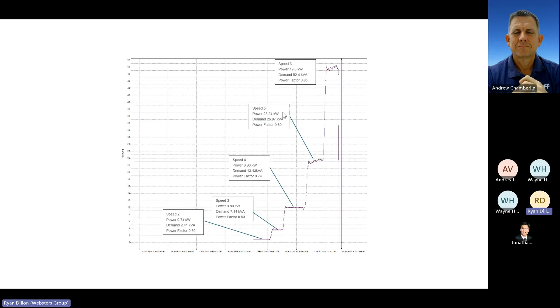And as you reduce the speed, the power factor dropped, which means proportional to the kilowatt demand, the kVA instantaneous demand increased. So what you're seeing in this scenario is an interesting discussion with a grower or a farmer. Hey, do you want to reduce your fan from speed 6 to 5? Did you actually realize that just reducing it by 1/6 in this instance, based on the configuration, almost cut the energy use in half? Now, having this attention to detail and this granular focus reveals things.